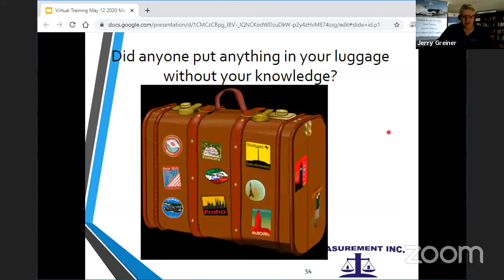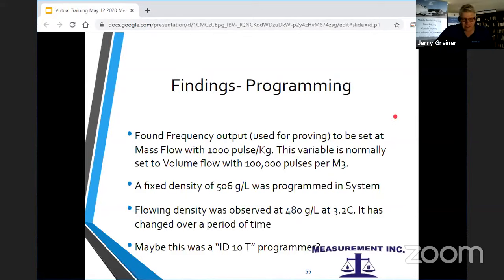Sometimes when you go through the airport, they ask you a question which always seems to not make sense: did anyone put anything in your luggage without your knowledge? Well, if it was without my knowledge, how would I know about it? Well, in here we found that sometimes putting things in without your knowledge also happens. There's a frequency output that's used for proving. Normally it's set on pulses per cubic meter, 100,000 pulses per cubic meter. It was set at 1,000 pulses per kilogram.